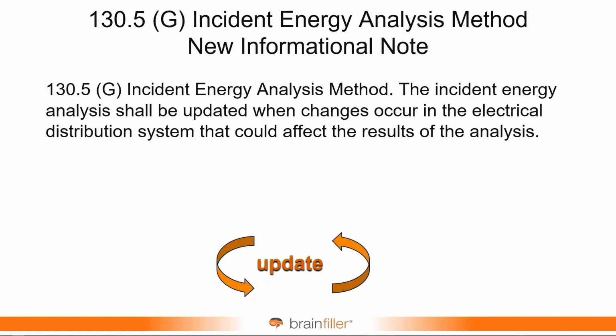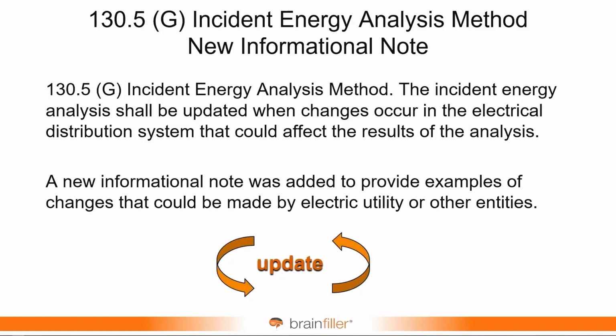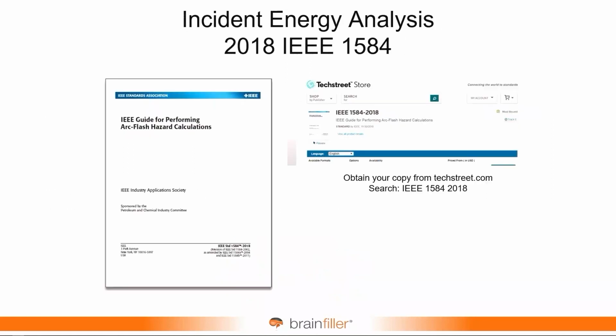The incident energy analysis, NFPA 70E says, needs to be reviewed if there are changes that could affect the results. So the incident energy analysis shall be updated when changes occur in the electrical distribution system that could affect the results of the analysis. There's a new informational note that was added to this, and it lists examples of changes that could be made by the electric utility or other entities. When someone is performing an incident energy analysis, it's going to be based on IEEE 1584, and that's how you calculate the incident energy.